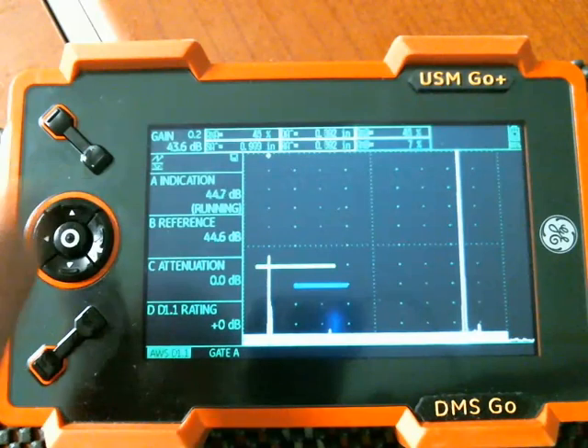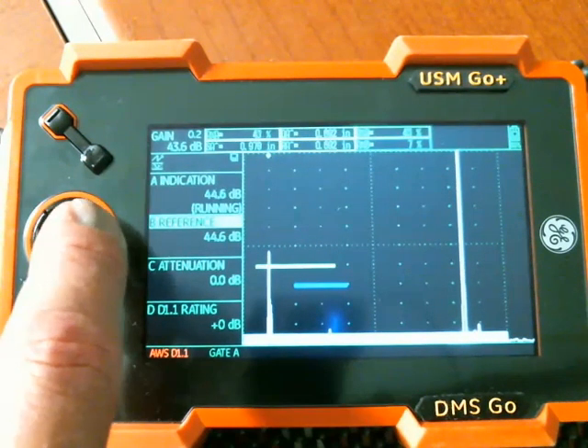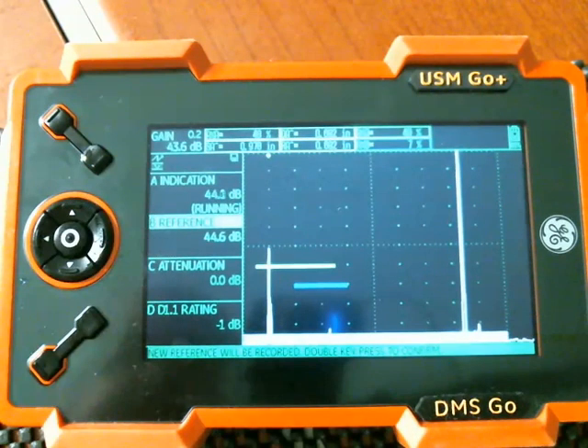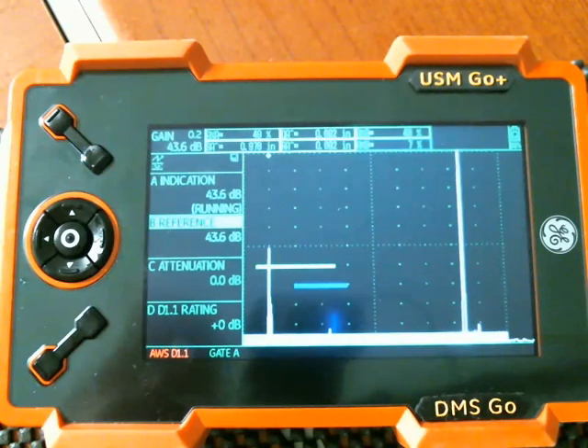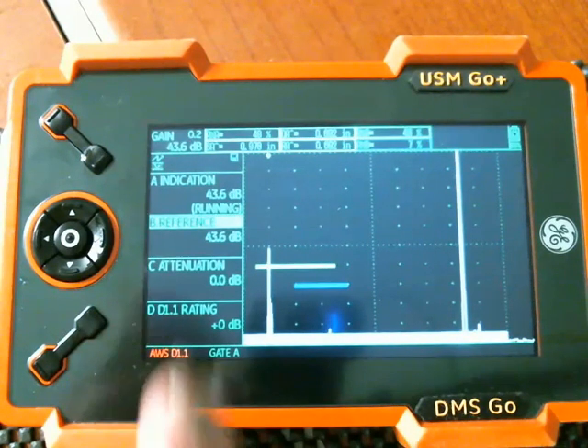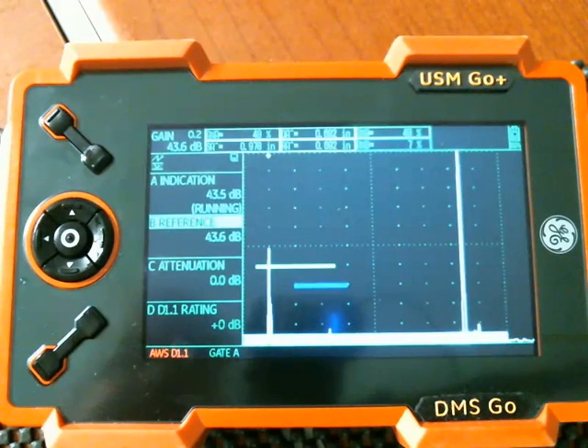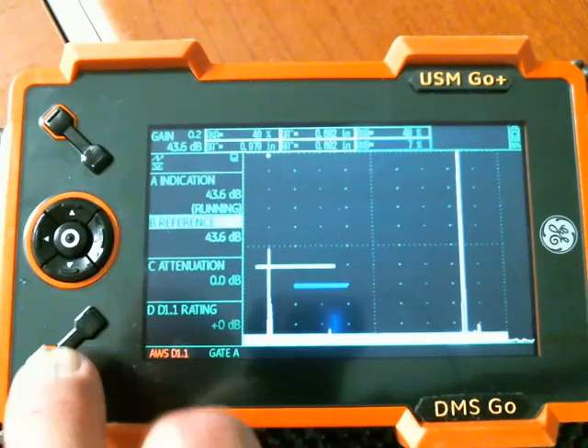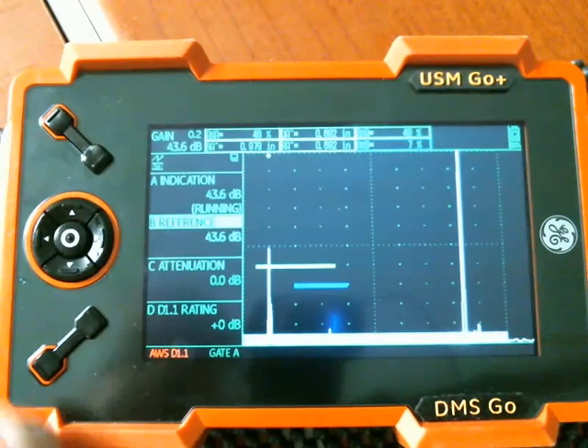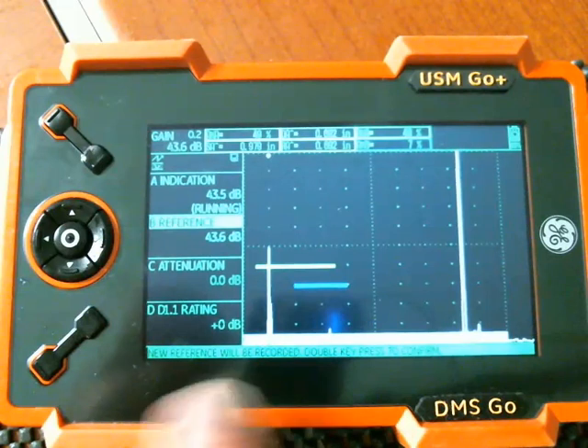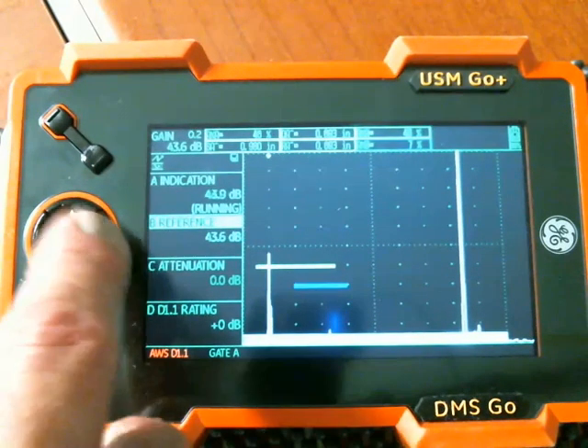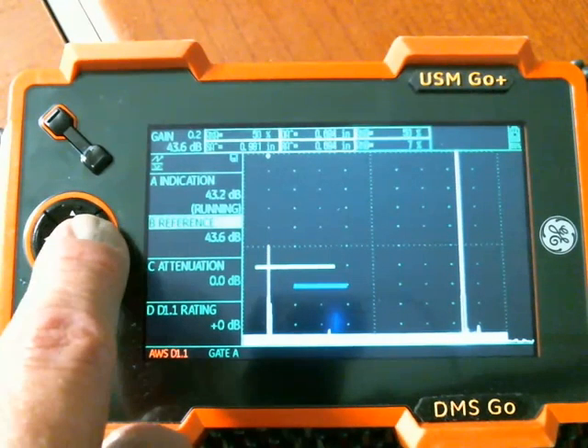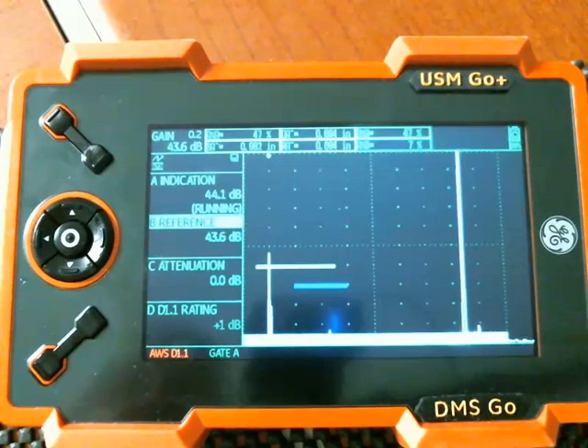Go back to AWS D1.1. Go up to the B reference. Peak up again. And record to reference. And you'll notice when, because I already had a reference programmed in from a previous run, when I input the reference, when I did the right click to input the reference, it asked me to confirm that with a double key press. That means press these two ends of the rocker switch, press both at one time. So again, we're going to go right to record. New reference will be recorded. Double key press to confirm. Double key press. So right. Double key press to confirm. Now at this point, the AWS calculator is up and running.